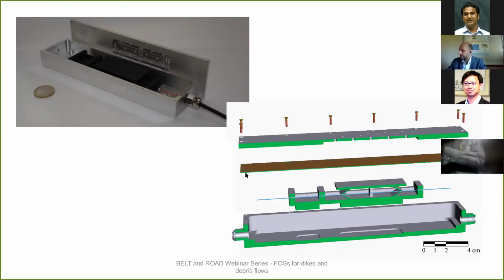One note about the brown sheet that you can see here: it is a rubber that is devoted to making the case waterproof and to transducing the pressure that comes from outside through this hole on the top cover of the aluminum case. So the water can go inside these holes, push the rubber membrane, and then exert an elongation of the fiber that is embedded within the transducer itself.